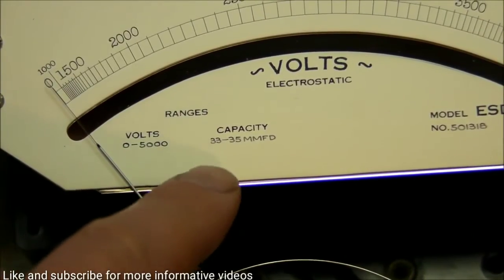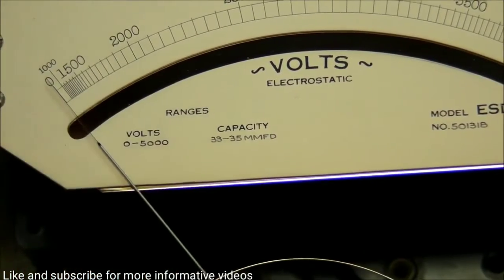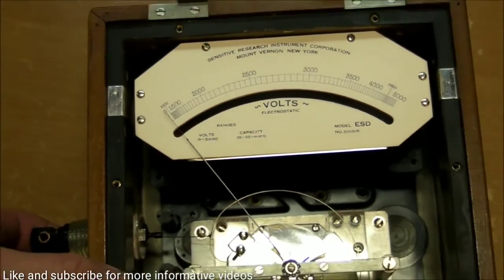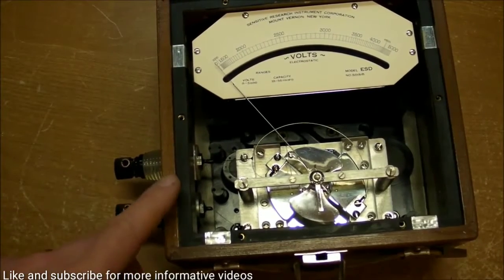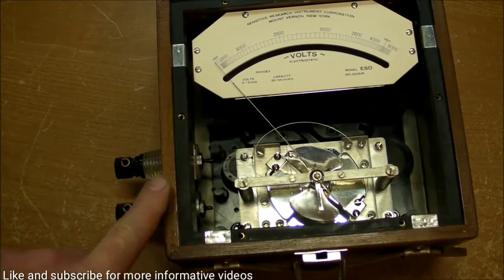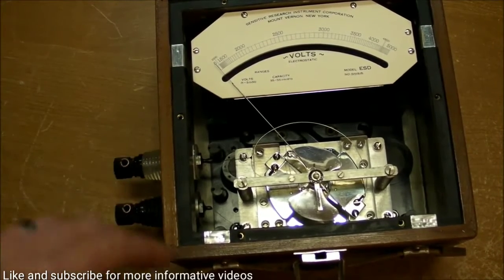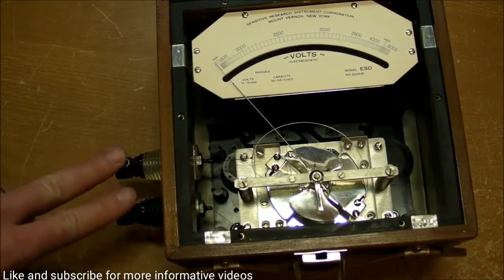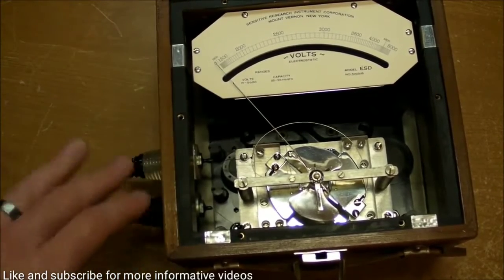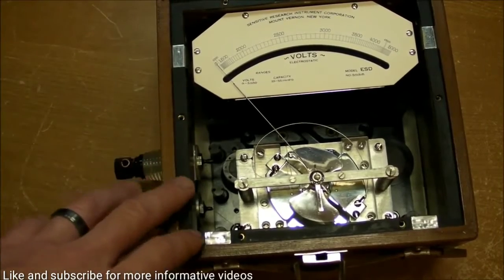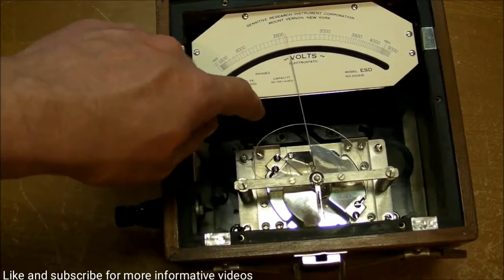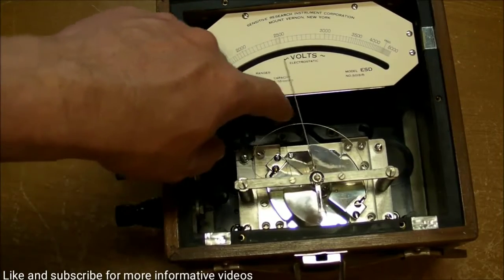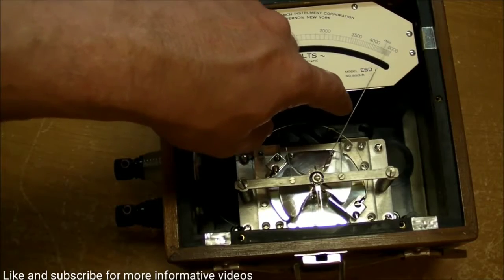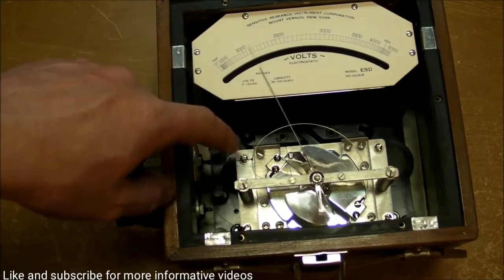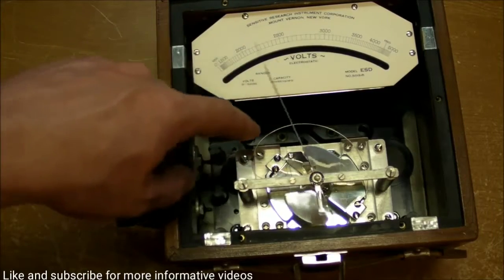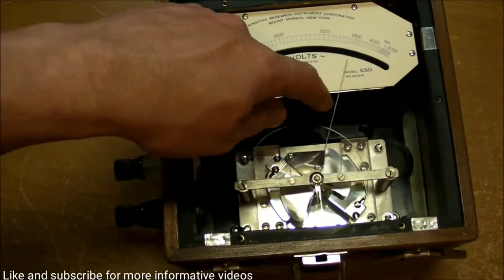Now let's have a look at this capacity measurement here of 33 to 35 picofarads as measured back in 1954, 61 years ago. When I measured this thing with two different digital LCR meters, I got pretty much the same result of 12 picofarad, give or take half a picofarad or so. Not that much of a difference, and that's going straight across these two terminals into the box. Doesn't matter what the polarity is because it's an AC measurement anyway. And I got 12 picofarads, and even if I gently move that needle either with my finger or with some kind of insulated plastic rod, it really varies anywhere from 11 to 12 picofarad regardless of where I put the needle and the corresponding plates down here.